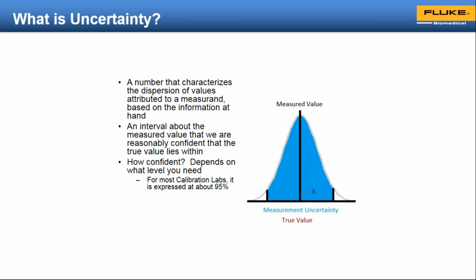If you send your test instrument to a calibration laboratory like those operated by Fluke and Fluke Biomedical, we express our confidence value at about 95%. That is, we are 95% certain that the values we're going to look at for calibration and accuracy of that test instrument are able to be achieved. That extra 5% represents the uncertainty around those. So I hope that clarifies what uncertainty is.